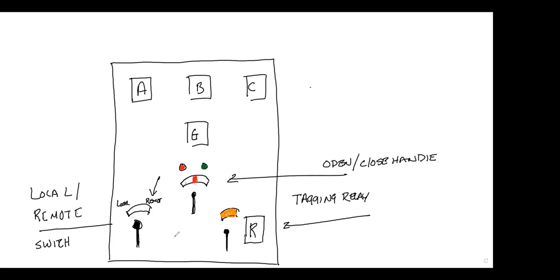Okay. I want somebody to remotely operate this breaker and have control of it. If I need to come to the breaker and do something inside, I don't have SCADA operation, or they're too busy doing something else for a long duration of time, I need to turn it to local. There's only one thing in remote, and this is a safety feature: only breaker open works. That's a safety feature. In remote, I can walk in, I can turn the middle handle to green, the breaker will open. That's all it will do in remote. Otherwise, anything I have to do in this thing, I have to turn it to local.